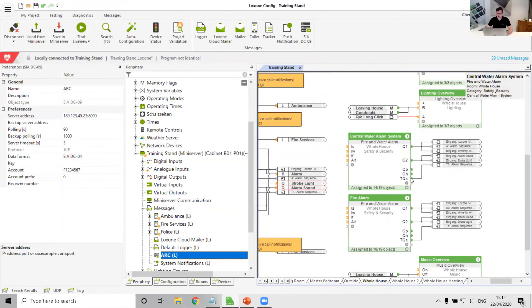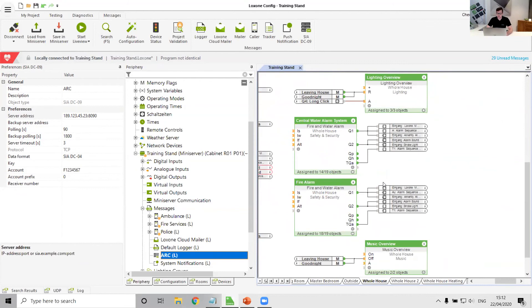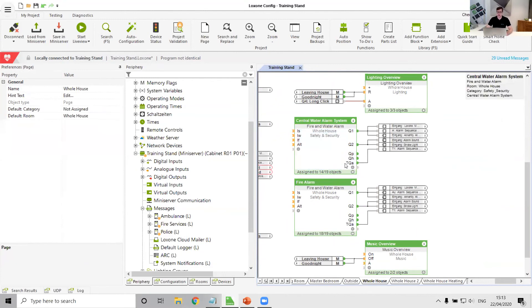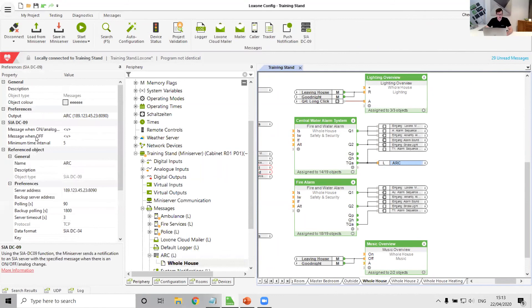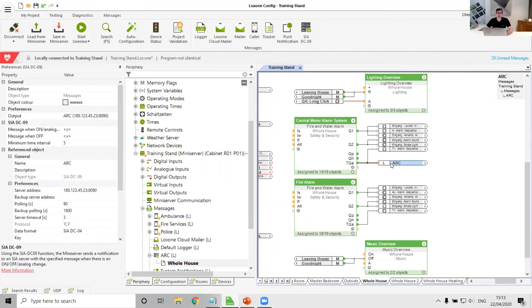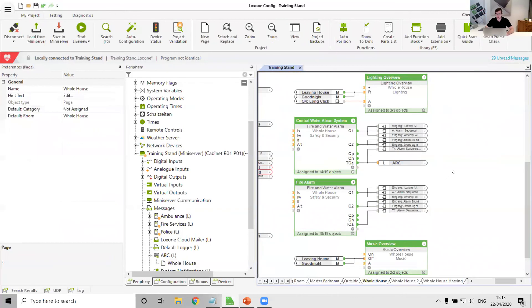Once you've put that in, you find the block you want to link this to - most likely something like the central fire alarm, water alarm block, or alarm sequence - and link it to the text output. Just like any other message in Loxone, you can specify the message per event, and it will pass through the exact text that comes out, such as the last alarm triggering event. That exact text is what the alarm receiving center sees on their screen. So when they're going through the key holders list they can say: fire alarm has gone off at 15:13 on the 22nd of April - it was the fire detector in the kitchen.